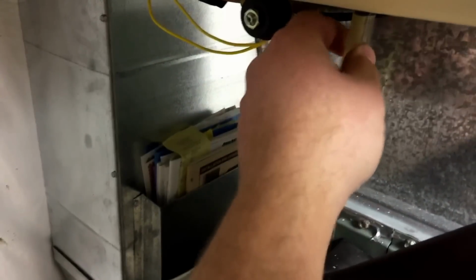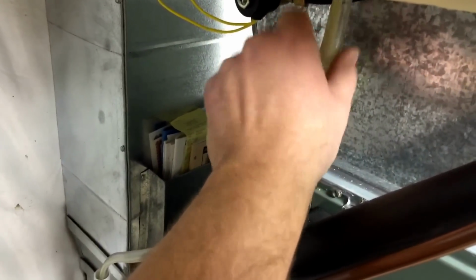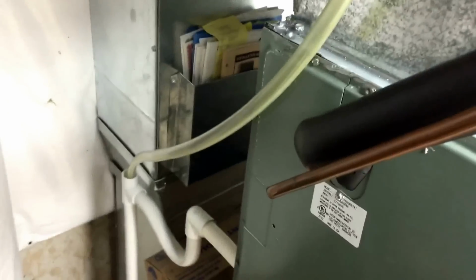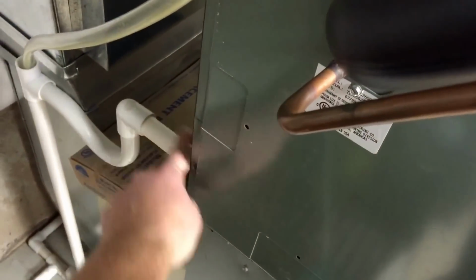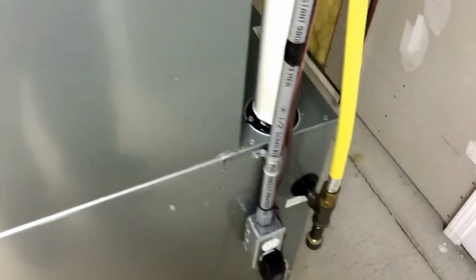Another thing I find too is condensate drains. This is 3/4 inch PVC piping. Around here, right here, we have a condensate drain coming from this humidifier. This is 3/8 tubing. Now this is fine for a humidifier because this water is running constantly when it's on.